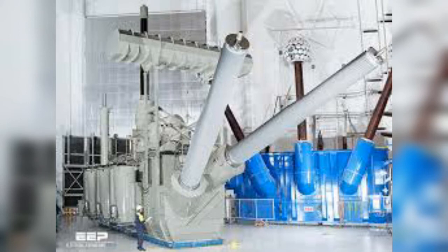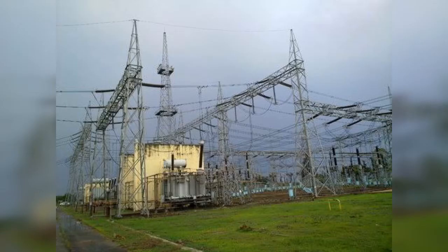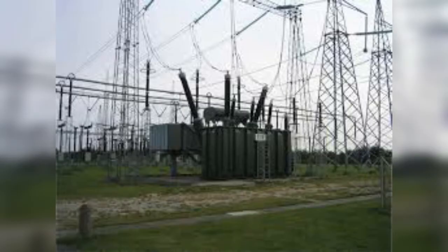The suggested design consists of a double bus bar and double disconnecting circuit breakers. The disconnecting circuit breaker, DCB, is a disconnector function integrated in a circuit breaker, replacing the conventional combination of a circuit breaker and a separate disconnector.